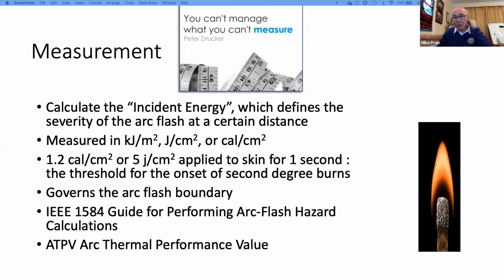Kilojoules per meter squared is a true SI unit, although calories per square centimetre seems to be the favoured currency for arc flash PPE. For today's purposes, I'll probably stick to calories per square centimetre and perhaps think as well about joules per centimetre. But it also governs the arc flash boundary. In this case, 1.2 calories or 5 joules per square centimetre applied to the skin for 1 second is the threshold of the onset of a second-degree burn.